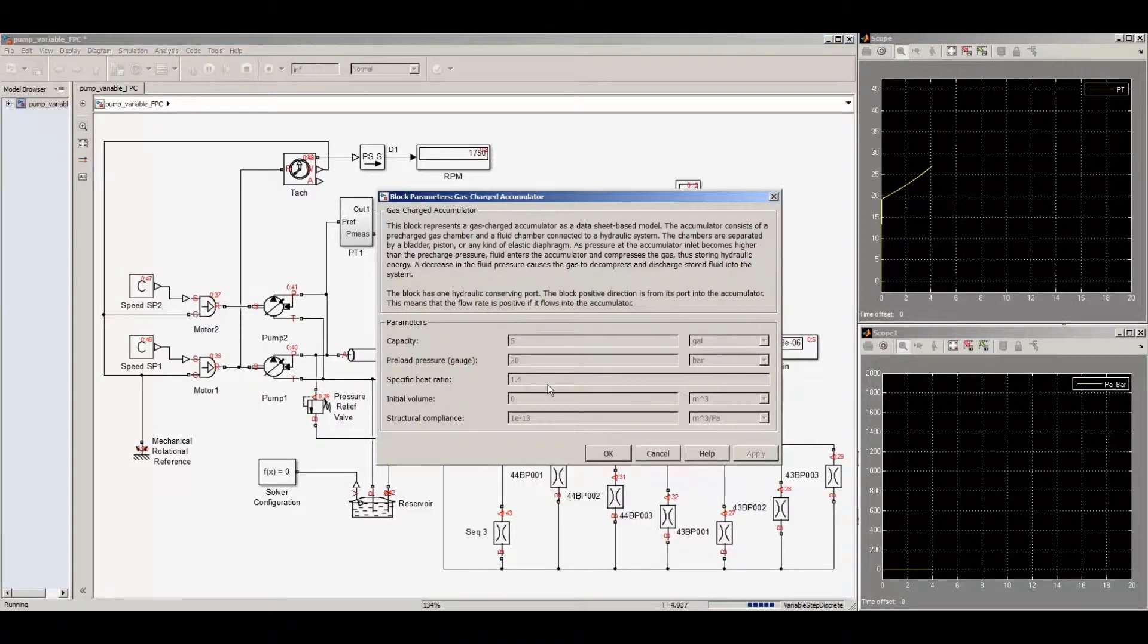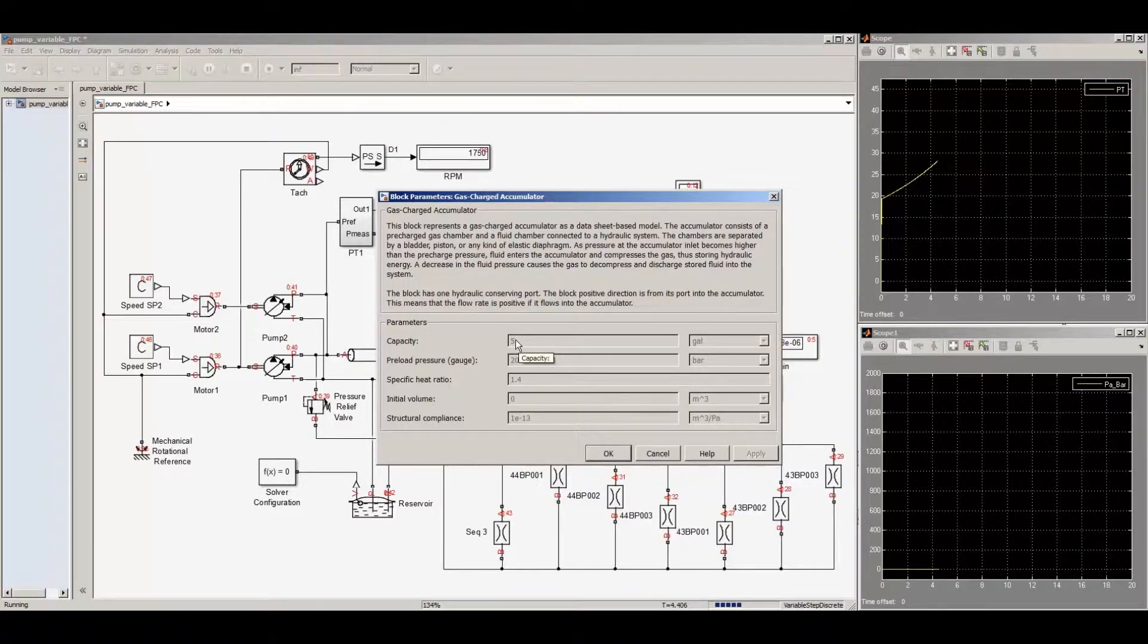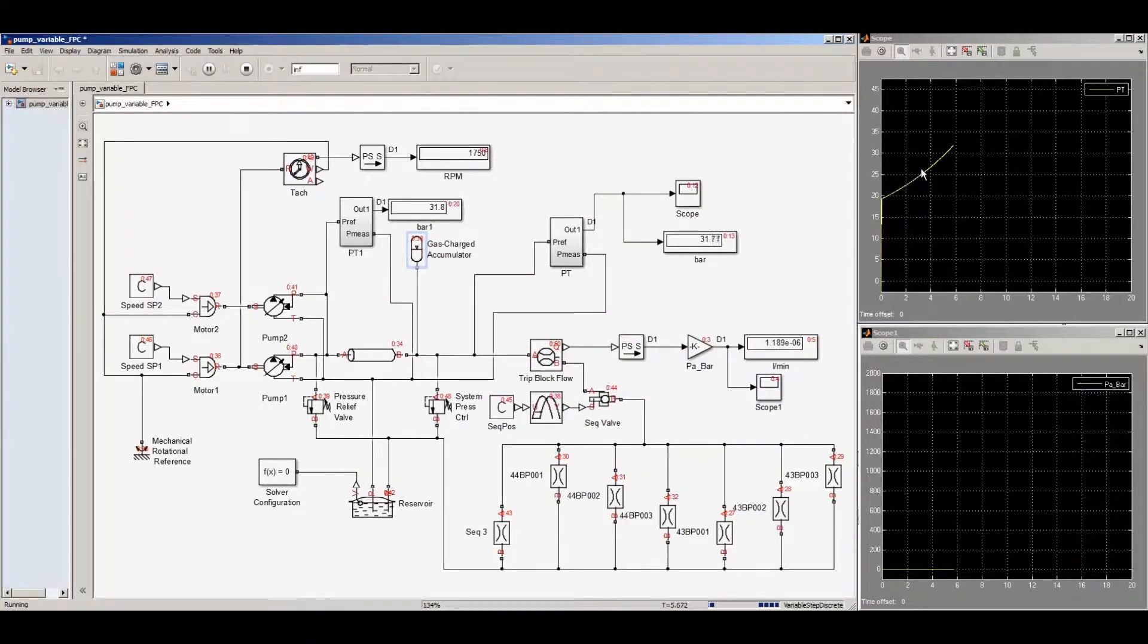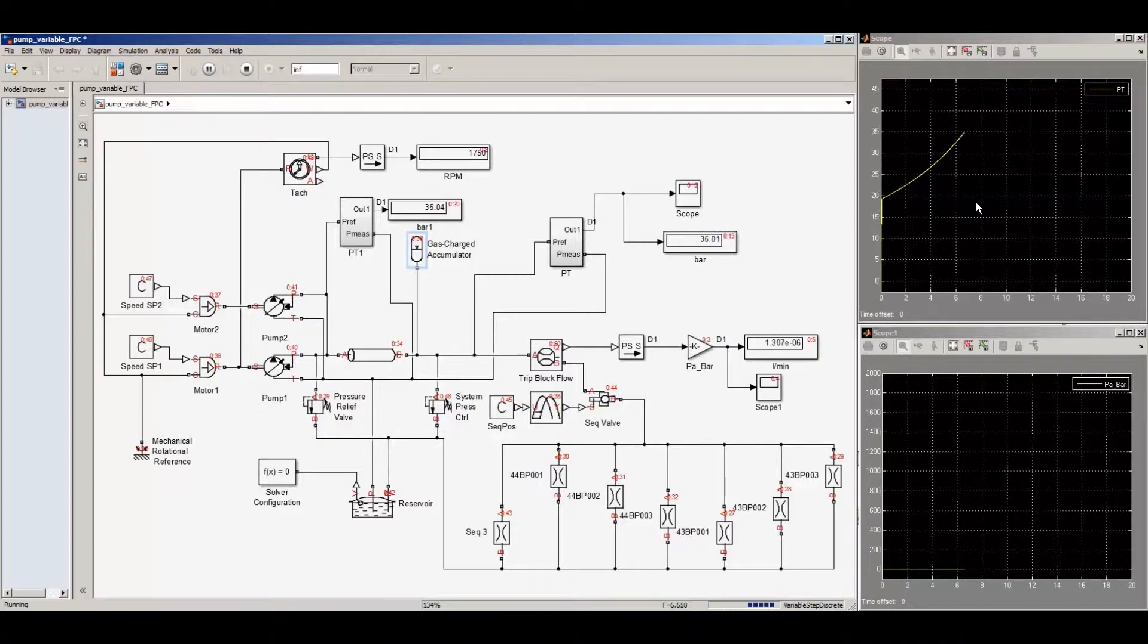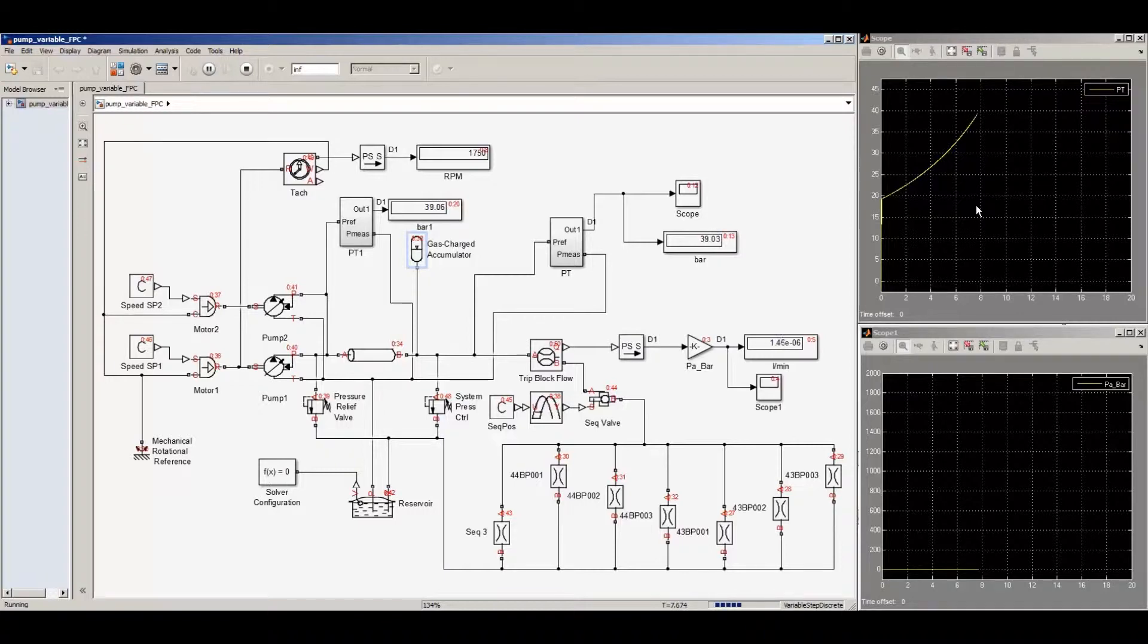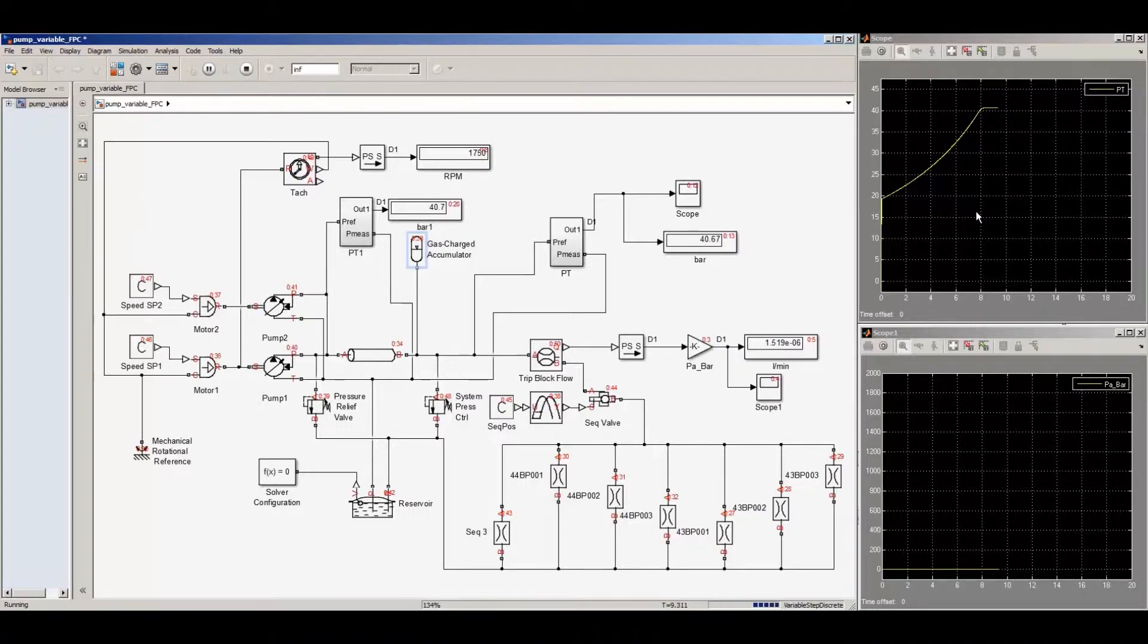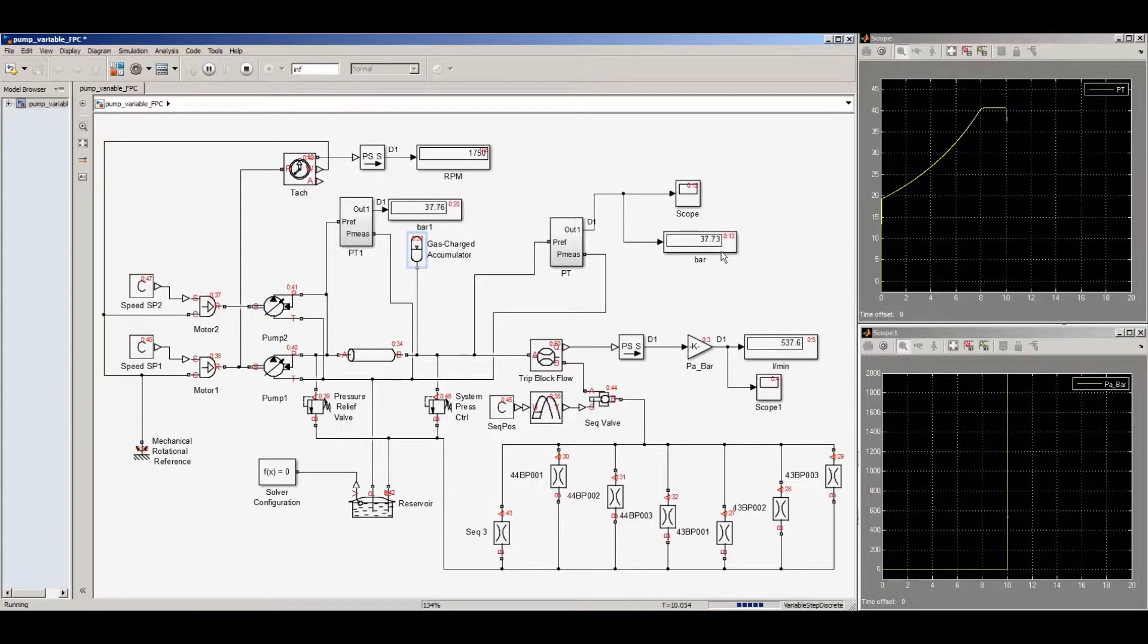Starting the simulation, we see the effect of the accumulator. We've modeled a 5 gallon accumulator with a 20 bar pressurization, so when we first start the pump, the pressure will not rise immediately until the accumulator is fully charged. Once we hit the set point of the system pressure control, the pressure no longer rises. We stabilized it around 40 bar.